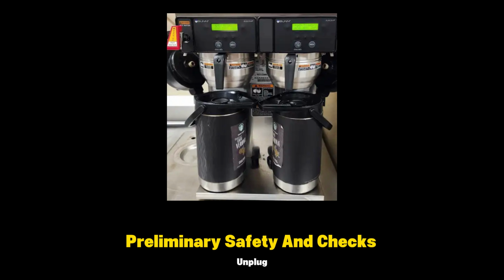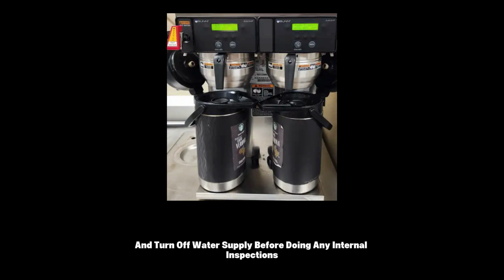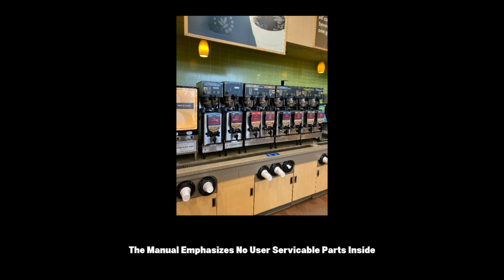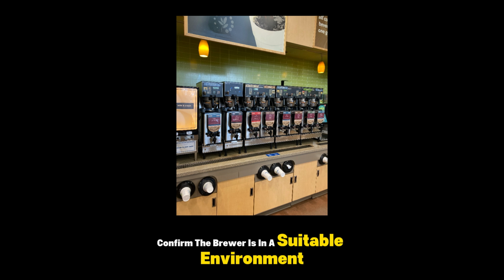Preliminary safety and checks: unplug, disconnect power, and turn off water supply before doing any internal inspections. The manual emphasizes no user-serviceable parts inside. Only qualified service personnel should open the unit. Verify the unit is properly connected: power supply, water supply, correct voltage, circuit breaker not tripped. Check the installation: correct water pressure, typically 90 psi, proper plumbing, no kinks in lines.